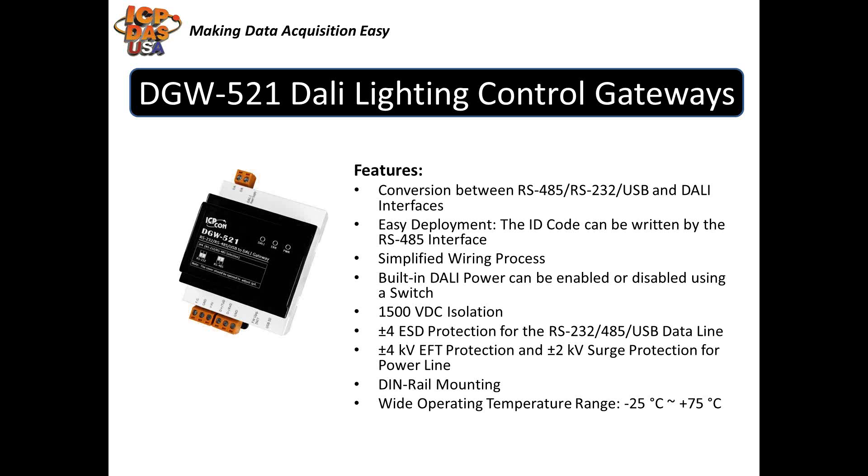DGW-521 is really easy to set up and use. It's set up with DCON Utility, a free PC-based configuration software that we provide. You can use it to set the serial address, baud rate, checksum, and parity. You wire directly to the USB and serial devices through the terminal block at the bottom of the DGW-521. You wire directly to the DALI network through the terminal block at the top of it. It also has built-in DALI power, as well as plus 4 ESD protection for the RS-232, RS-485, and USB data lines. Built-in DALI power can be used to power DALI devices. The power can be enabled or disabled with a switch on the DGW-521.